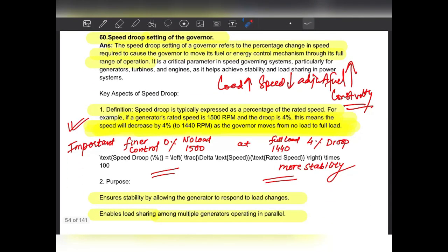Basically, let's suppose some generator has 4% droop or 3% droop. What is the meaning of this droop? Let's suppose your generator rated RPM is 1500 and droop is 4%. If you do the mathematics here, 4% of 1500 is 60. Then you subtract 1500 minus 60, and you will get 1440.